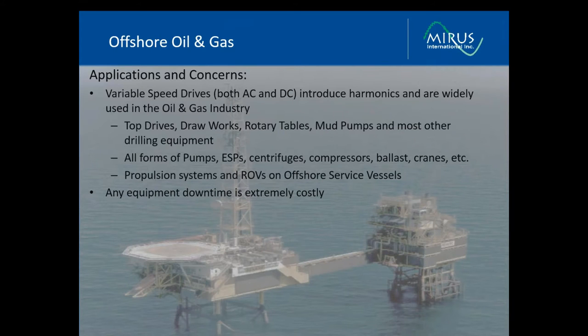The offshore oil and gas market has another unique set of challenges and safety concerns. Again, the power systems are typically very weak, generator-based, which creates high voltage distortion levels. There are also large numbers of nonlinear loads and variable speed drive operations for the drilling package and pumping equipment, including devices such as top drives, draw works, rotary tables, mud pumps, etc. So a lot of loads, and by far the majority of the loads on an offshore drill rig or production platform are nonlinear harmonic generated.